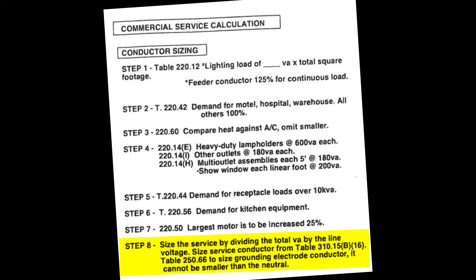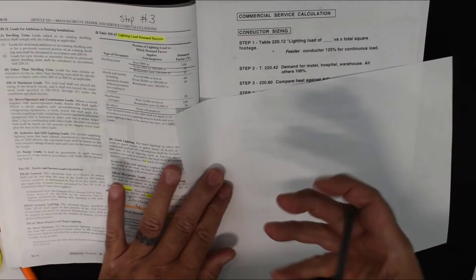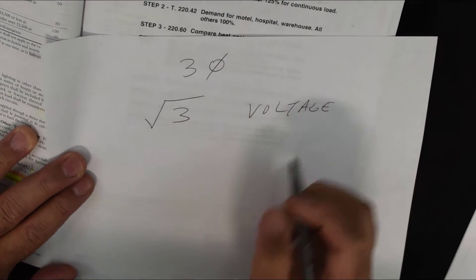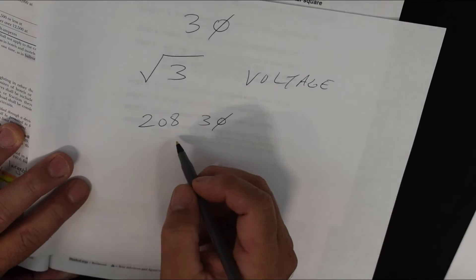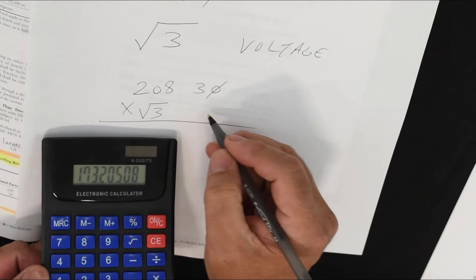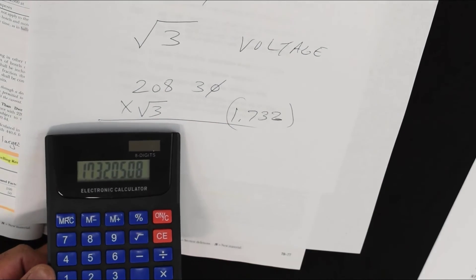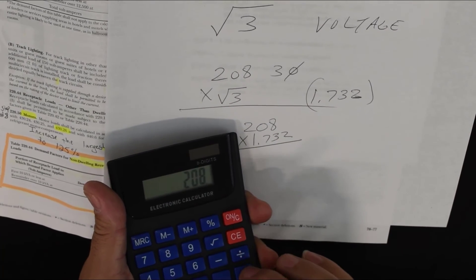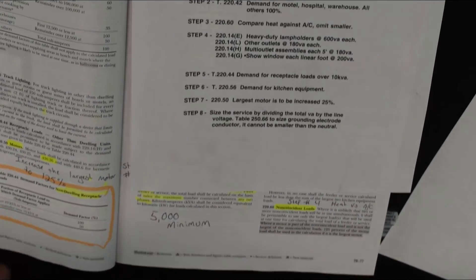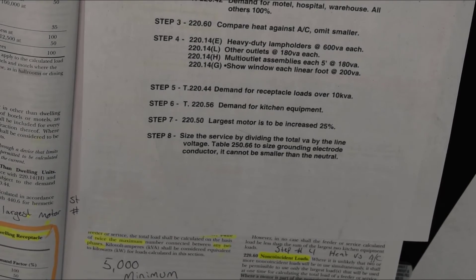Step 8 is to add everything up and divide by the line voltage. For a 240-volt system, you divide by 240. Most commercial buildings use a three-phase system, and on a three-phase system you must apply the square root of three to the voltage. For example, on a 208-volt three-phase system, you divide your total load in VA by 208 times 1.732 — which equals 360.256 — not by 208 alone. So your total load in VA is divided by 360.256 for a 208-volt three-phase system.